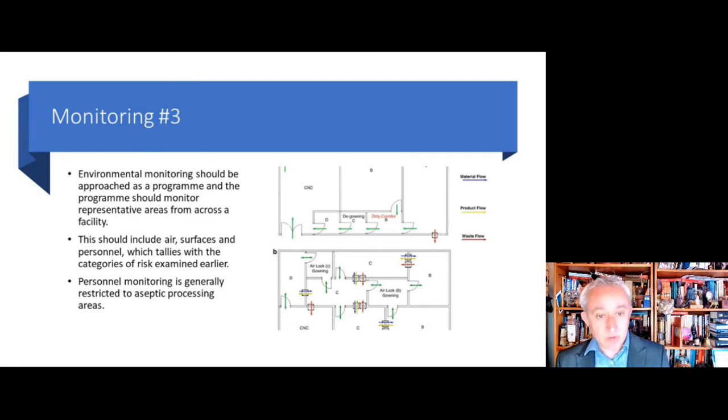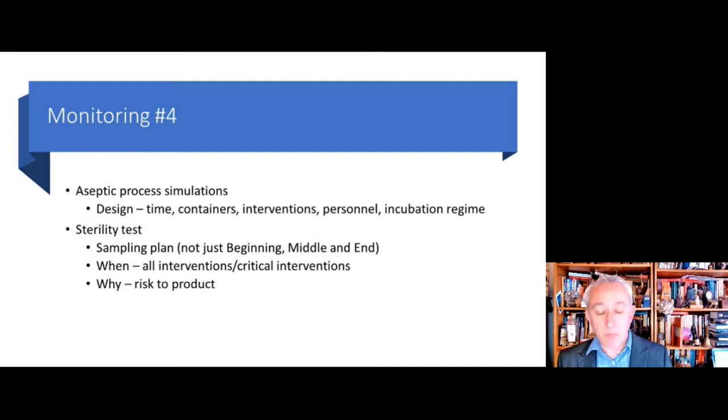But we need to monitor where we have control weaknesses, and that should be a risk-based program. We should understand that any environmental monitoring is limited in terms of recovery, in terms of the limitations of methods, in terms of the small sample sizes taken, due to the presence of organisms that are either naturally unculturable or in a physiologically stressed state. The key thing about environmental monitoring is the importance of trending. Often single results don't mean too much. It's the overall pattern, the picture of those results coming together that matters. Just to illustrate the process standing process flow point, there are some simple diagrams about looking at people flow, equipment flows, waste flows, and understanding the times these happen, the number of people involved, the types of things transported. This can help construct a more meaningful environmental monitoring program.